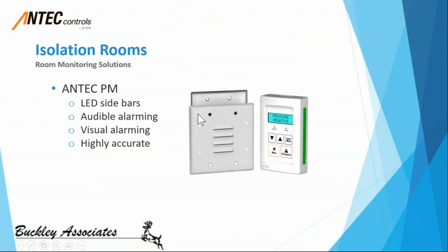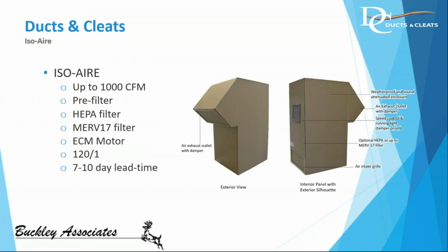The other room pressure monitoring, I'm switching back to Antec here just for a quick second. They're providing this on a 2-day lead time for any orders of 50 and less. So again, they have some more robust monitoring devices that we would usually recommend over this one. However, it does have every capability to monitor pressure in these temporary rooms. The really nice feature and the feedback we've gotten on this is this LED sidebar. So this green sidebar here is actually an LED strip, which changes between green and red depending on the pressure reading. And then there's also an audible alarm built right into this. So again, 2-day lead time for orders of 50 and less on these guys. So we've been seeing this thing utilized quite a bit.